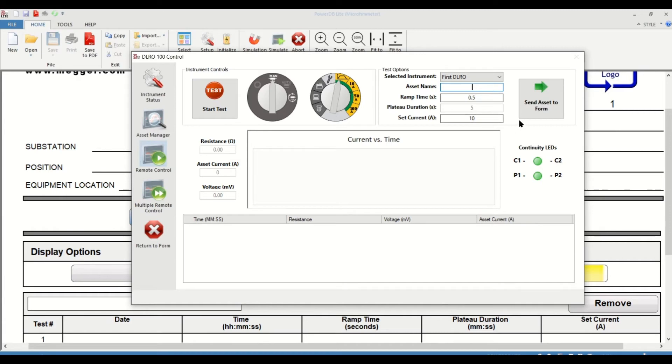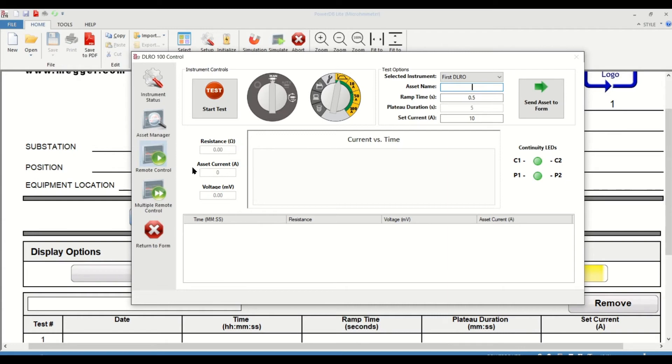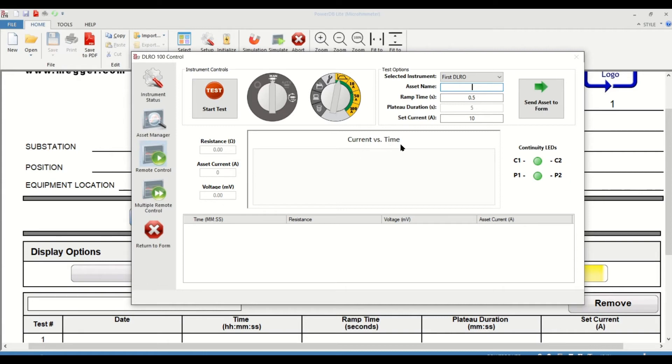You have this button to send asset information to the PowerDB form. If you move further down the screen, you have the resistance value that would be measured, the current that was passed through the asset, and the voltage that was measured. The resistance is going to be a calculation of the voltage measured divided by the current that's injected. You'll have a graph for current versus time, and we will see that once we initiate a test here.